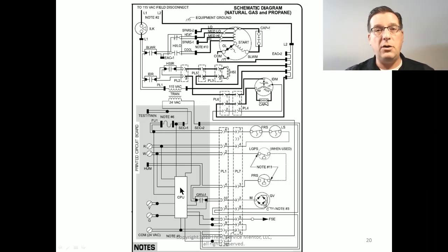And now you need to know what that is. What is the sequence of operations? What is the sequence of operations of any gas furnace? Well, the first thing that happens on a call for heat is the draft inducer starts, right? That is one of the outputs. Where does that output come from? Here's our draft motor. And we can trace backwards.